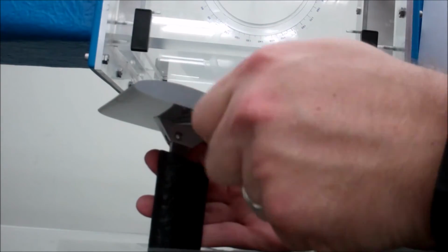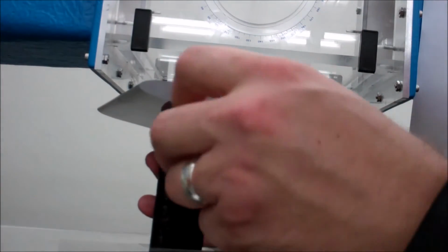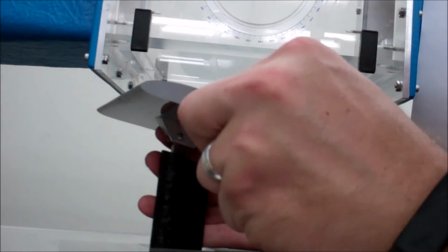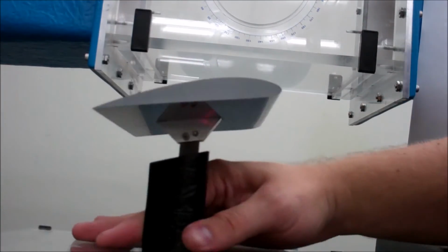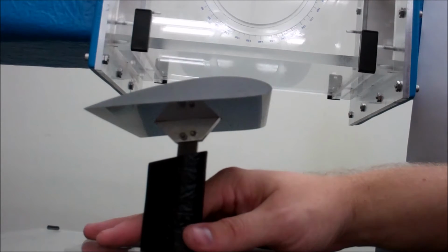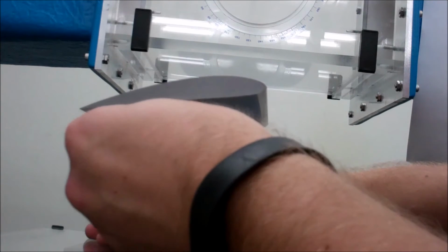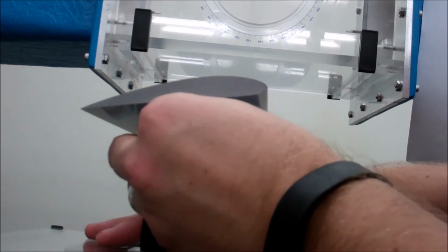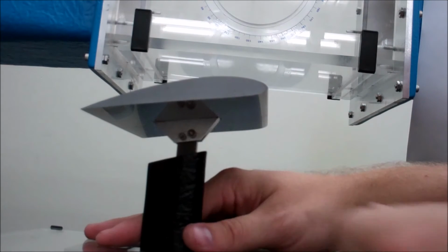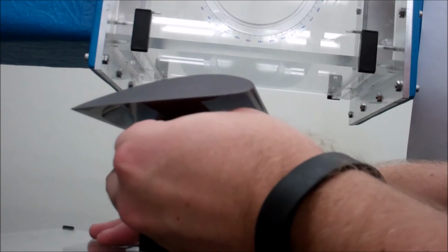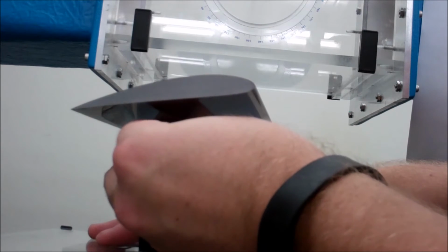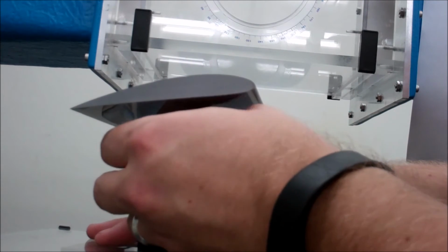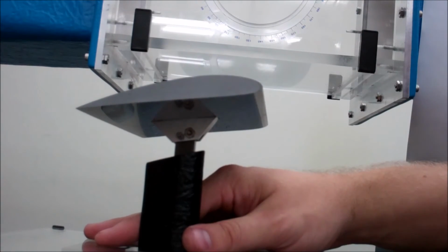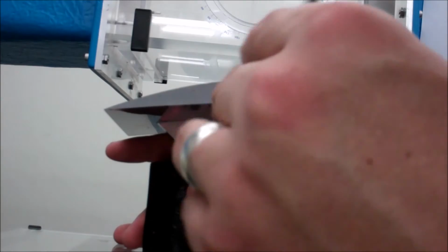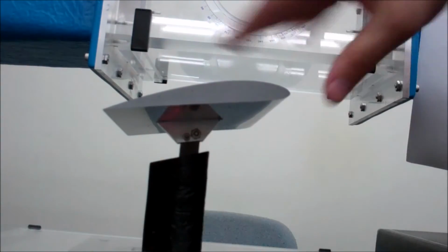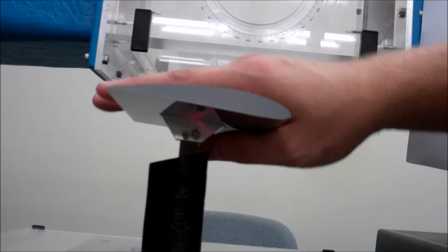And you want to make sure the bolt goes all the way through and that you do it hand tight. Then you're going to turn it around. Put the washer in on the other side. And then you're going to lightly screw the nut on. Before you put it in the unit, make sure you untighten the set screw here and make sure you're able to turn the airfoil. So I can turn the airfoil fairly easily.